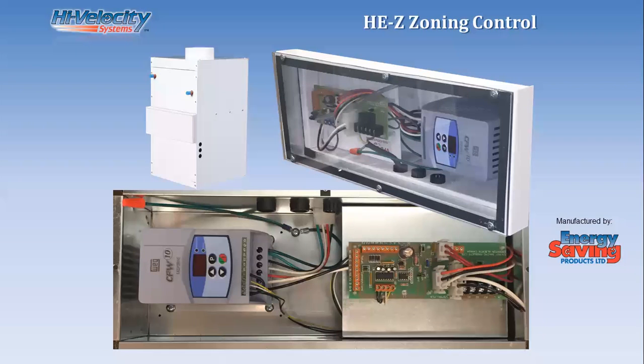We're using a variable frequency drive motor and control. The variable frequency drive gives us infinite variability with the airflow settings on our air handler. We have dials to control the air speeds up and down and set speeds independent. We can set our cooling speed up at 100%, the heating speed set anywhere from 70 to 80%. And then we always talk about running constant fan operation with these fan coils because of the energy efficiency that can be provided with running constant fan, but also the added indoor air quality benefits that can be achieved in structures by running constant fan with better, denser filter media.